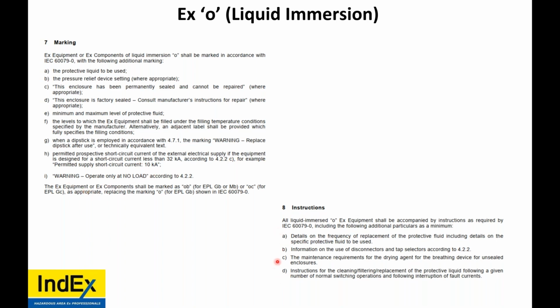Now, instructions, well, they talk about the frequency of replacement of the liquid, information for use of disconnectors and tap selectors. So if you have a multi-tap transformer, maintenance requirements for the drying agent for the breather device for unsealed enclosures, and instructions for cleaning, filtering, and replacement of the protective liquid following a given number of normal switching operations and following interruption of fault currents.